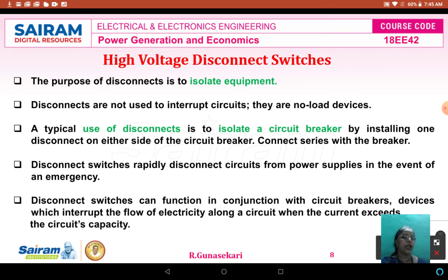That means the high voltage disconnect switches are used to disconnect the electrical equipment from the power lines which supply the equipment. Ordinarily, the disconnect switches are not operated when the current is flowing through them. They are opened mainly to isolate equipment from power lines for safety purposes. Most of the disconnect switches are the air break type, which is similar in construction to knife switches. These disconnect switches are available for indoor or outdoor substations, in both manual and motor operated designs.